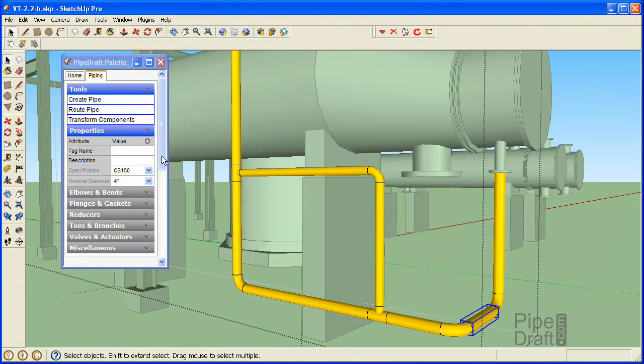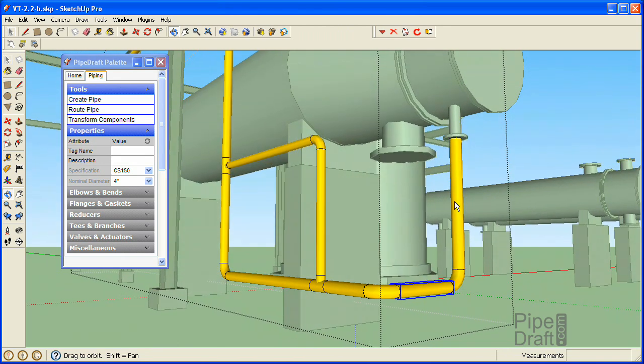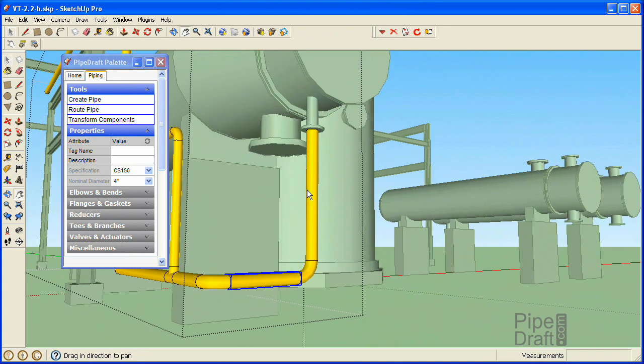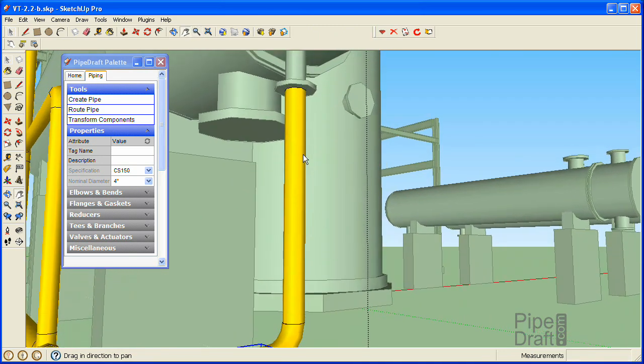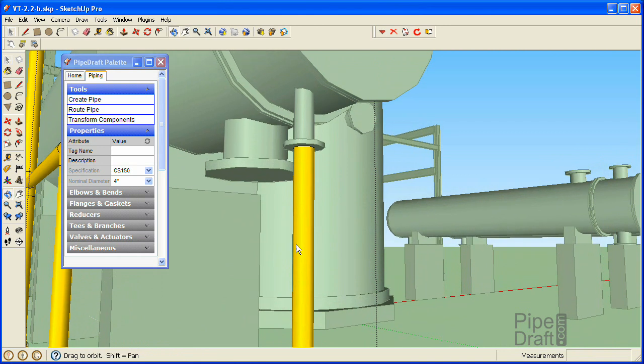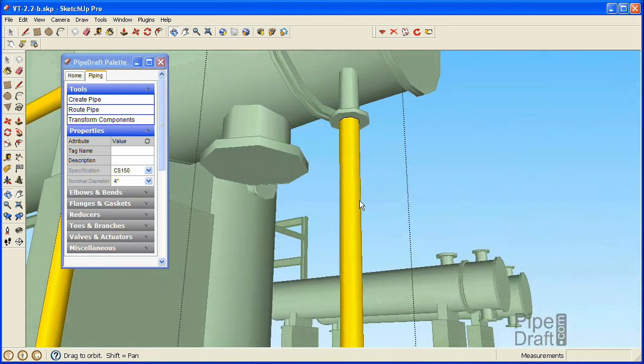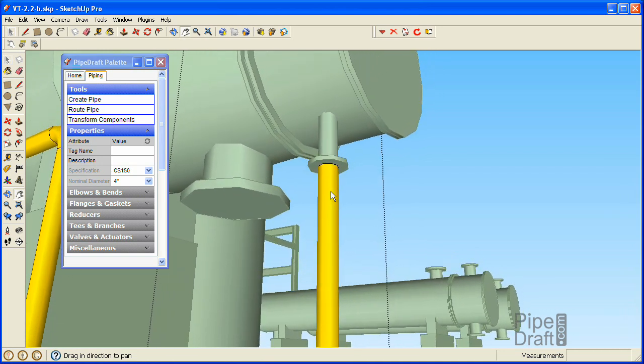It loads the matching components into the palette. It's important to understand that when we insert piping components, PipeDraft detects the nature of the piping component we click. If we click a fixed length fitting, PipeDraft will attempt to connect and orient the inserted component using the nearest matching virtual connect points. If the component we click is a pipe segment, then PipeDraft will either split or nibble away the segment to accommodate the length of the inserted component.